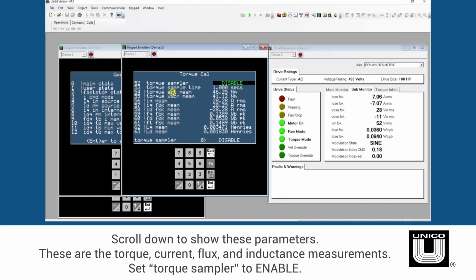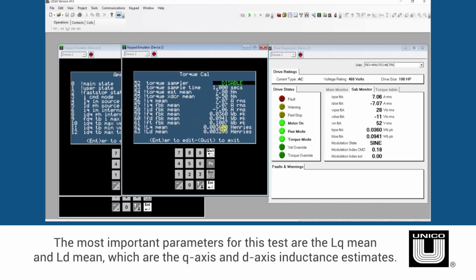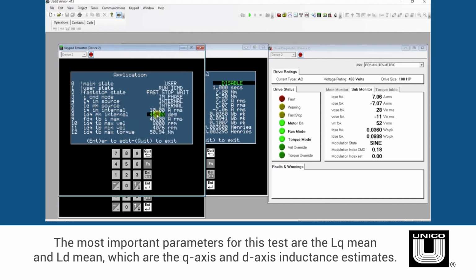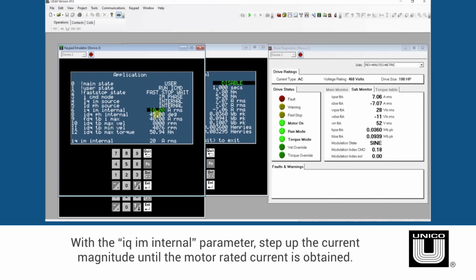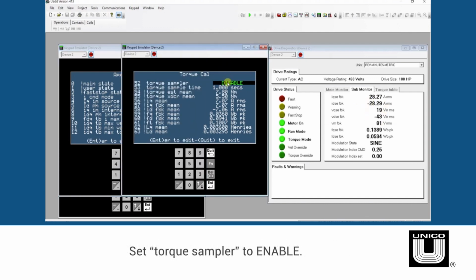Set the torque sampler from disable to enable. The drive will average the following parameters over the duration specified by torque sample time. The most important parameters for this test are the LQ mean and LD mean, which are the Q-axis and D-axis inductance estimates. Next, step up the current magnitude until the motor rated current is obtained. Once at the motor rated current, enable the torque sampler again.